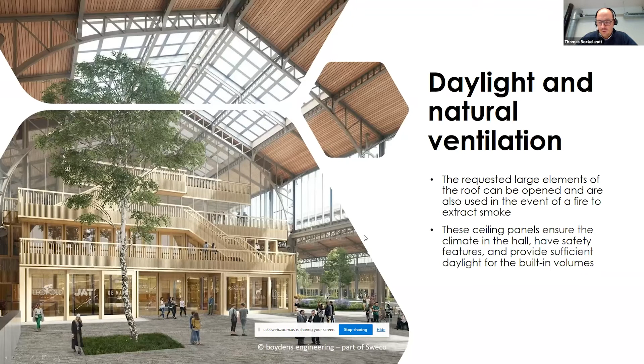It was decided the hall would not be climatized, so for the summer regime we needed large openings in the roof as well as a reasonable amount of openings at ground level at the site entrances, to create a natural ventilation flow in summertime. I asked for 600 square meters and got more than 2,000, because the fire department needed it to keep the large hall smoke-free in case of fire.